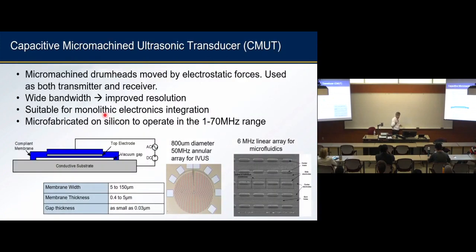So for the transducer aspect, what we use is capacitive micromachined transducers, called CMUTs. Basically, they are capacitive devices. You have a silicon wafer, and on top of that, you build a drum head, which can be in the order of 5 to 150 microns in diameter, depending on the frequency. If you think about a big drum head, like a meter in diameter, it resonates at 1 kilohertz. So if you want to go up to, say, 40 megahertz, you may just make that drum head 10 or 15 microns, and thin enough, and that gives you those ultrasound frequencies.